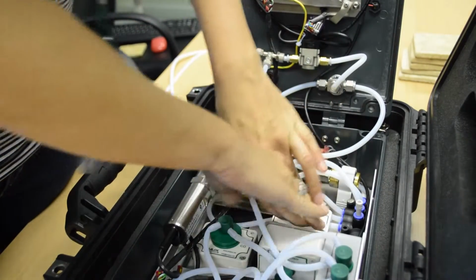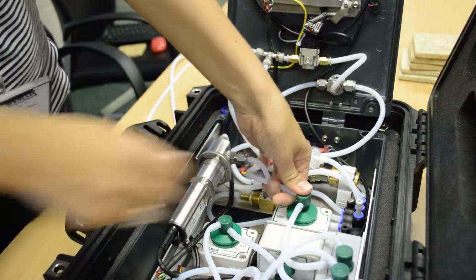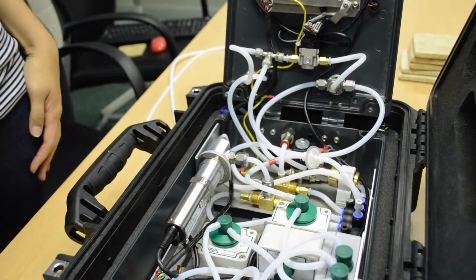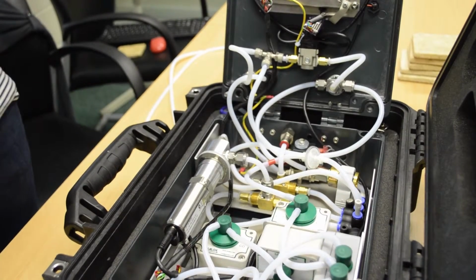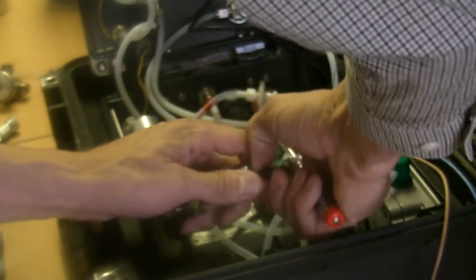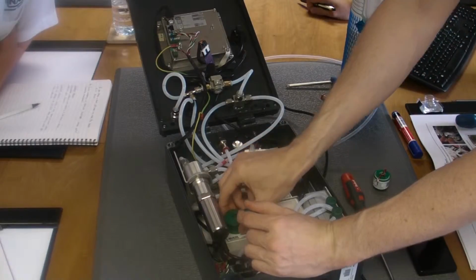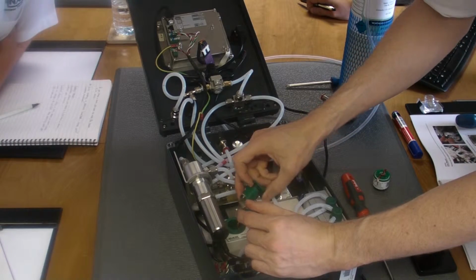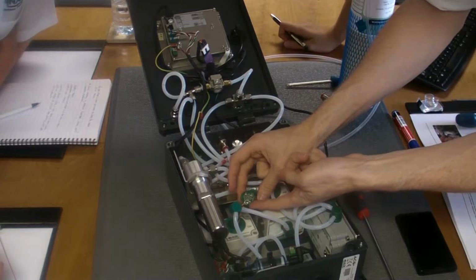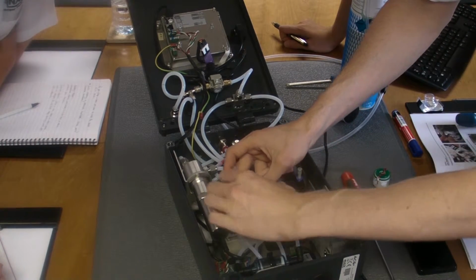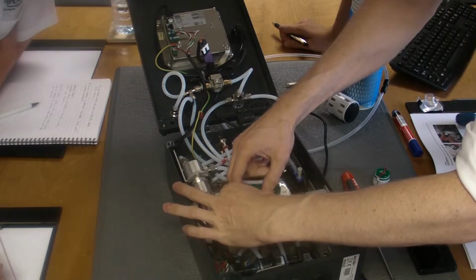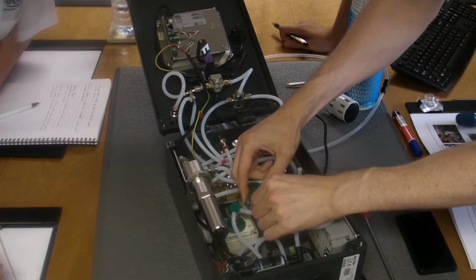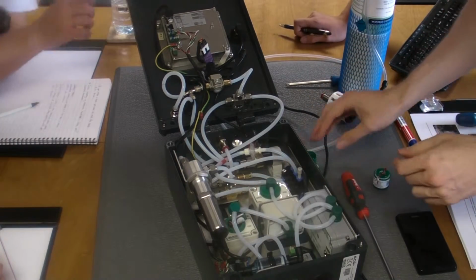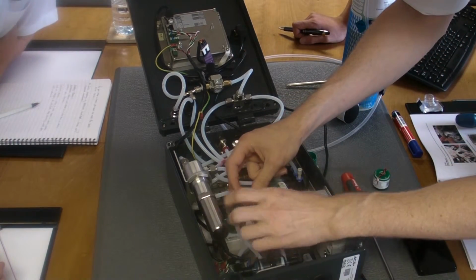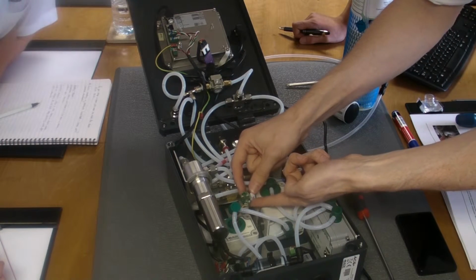Refit the enclosure lid and secure in place using the corner screws. Refit the flow adapter into the sensor inlet. Following an oxygen cell replacement, a full calibration must be performed. Again, remove the flow adapter from the sensor inlet. Use a flat blade screwdriver to pop out the cell holder from the sensor bulkhead fitting. Rotate the cell PCB connector clockwise to release from the cell holder. Disconnect the cell from the PCB connector. Connect the new cell to the PCB connector. Please note, it will only connect in one orientation. Fit the cell into the housing and rotate anti-clockwise to lock in place. Refit the cell holder in the sensor bulkhead and refit the flow adapter into the sensor inlet.